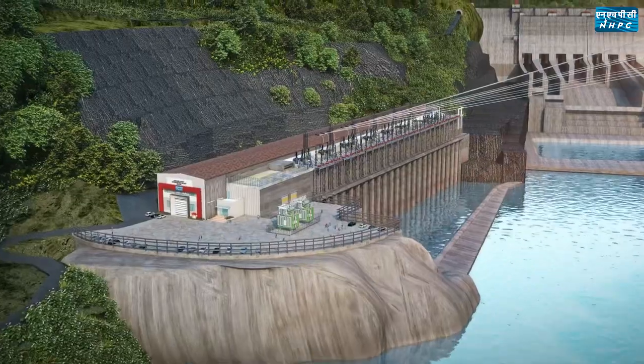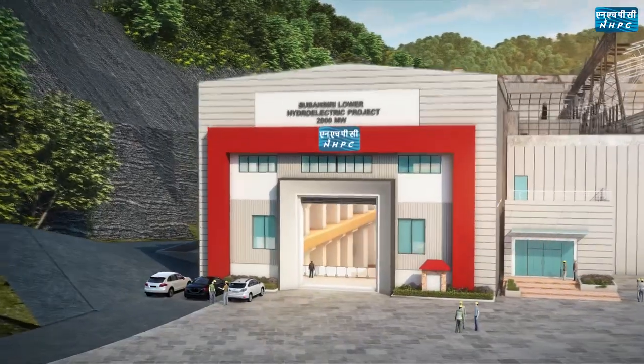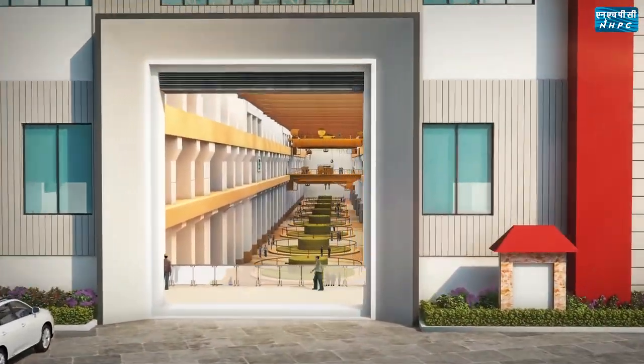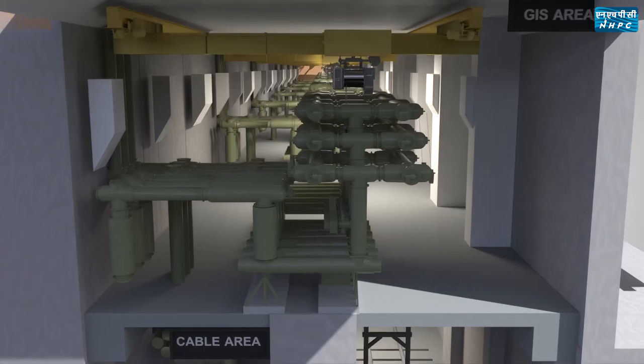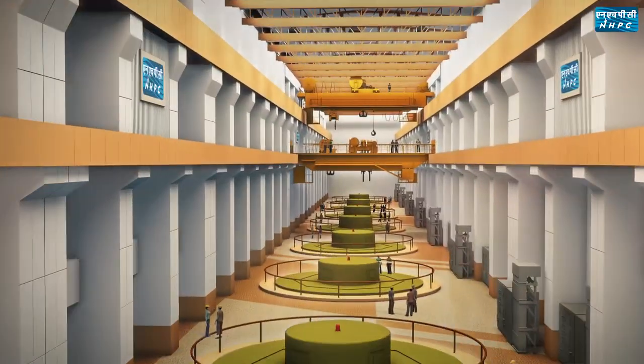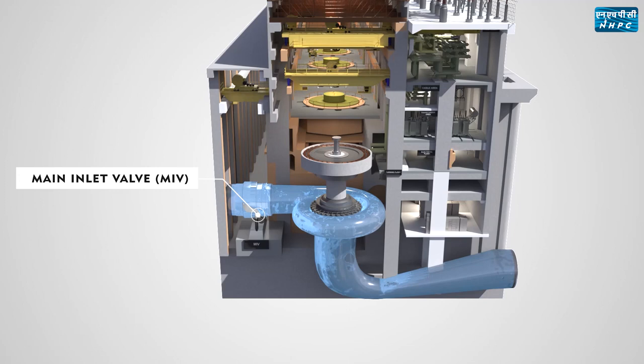The surface powerhouse of Subansiri Lower Project is located on the right bank of river Subansiri. The powerhouse is designed to house eight 250 megawatt machines, transformer bay, GIS block, and pothead yard. The auxiliary building, transformer bay, GIS, and pothead yard are located downstream of the main machine hall. To isolate the machine from the water conductor system, MIV has been provided in the upstream just adjacent to the machine hall.